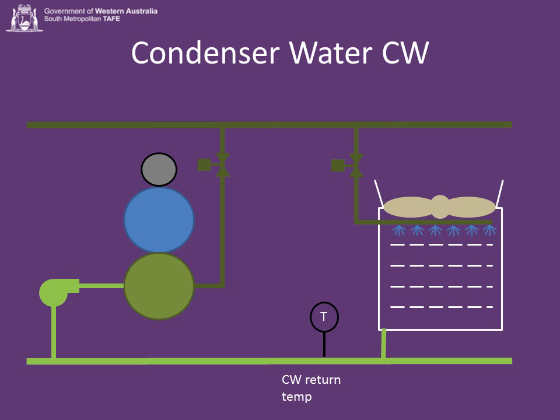The other side of the chiller gets hot. This is the condenser. The condenser gets hot. We pump water through the condenser using the condenser water pump into the condenser water header. That hot water, because it's hot, it's come through the condenser, is sent off typically to a cooling tower on the roof, where we cool it down through evaporative cooling.